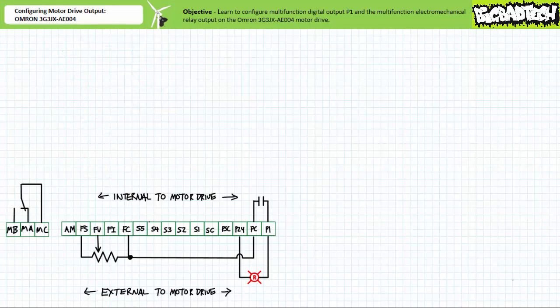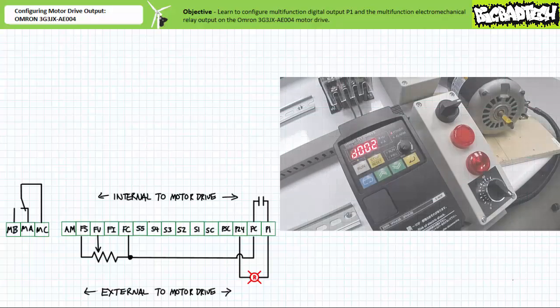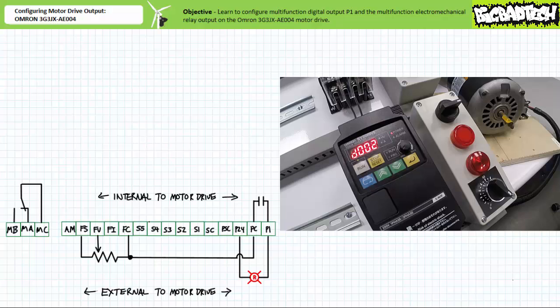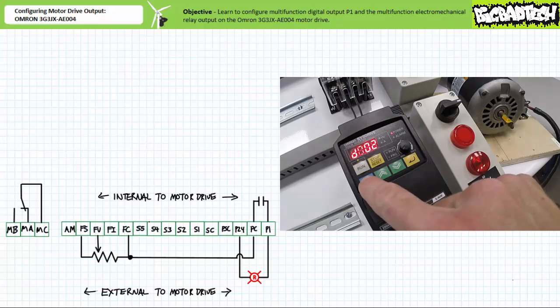Let's examine yet another function of multifunction digital output P1, 03, overload warning. First, we need to know what current this motor draws while in operation. Note I've disabled the pilot lamp for this portion of the exercise. With parameter D002, output current monitor, being displayed, when an operator presses run, during acceleration, current peaks out at around maybe 1.7-ish amps.